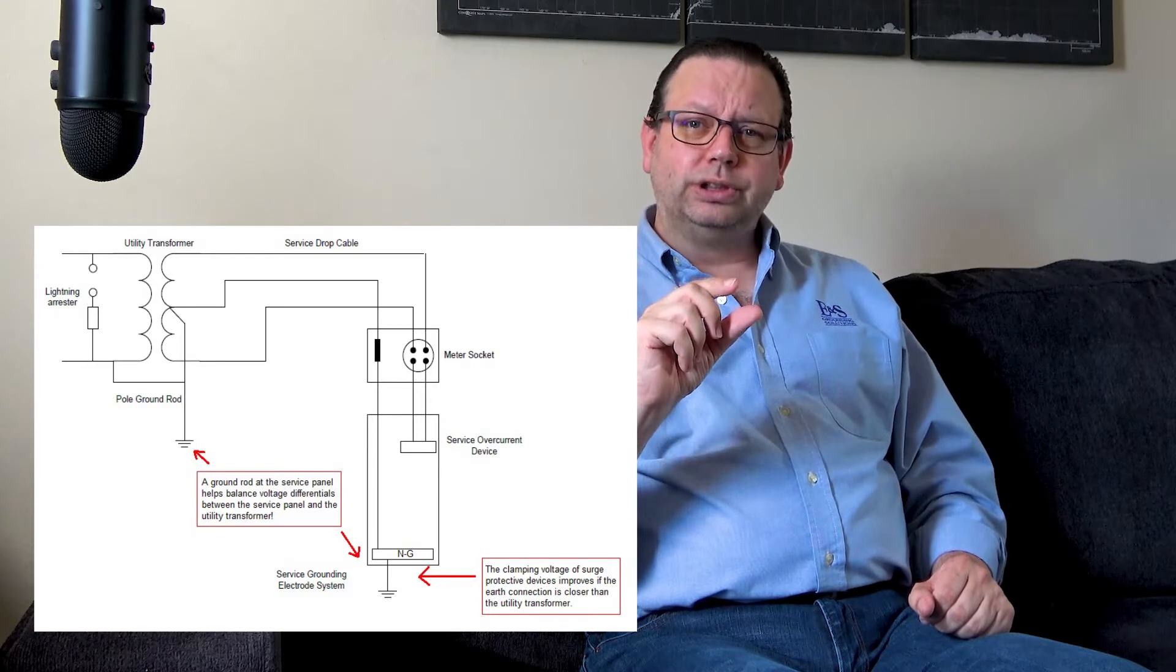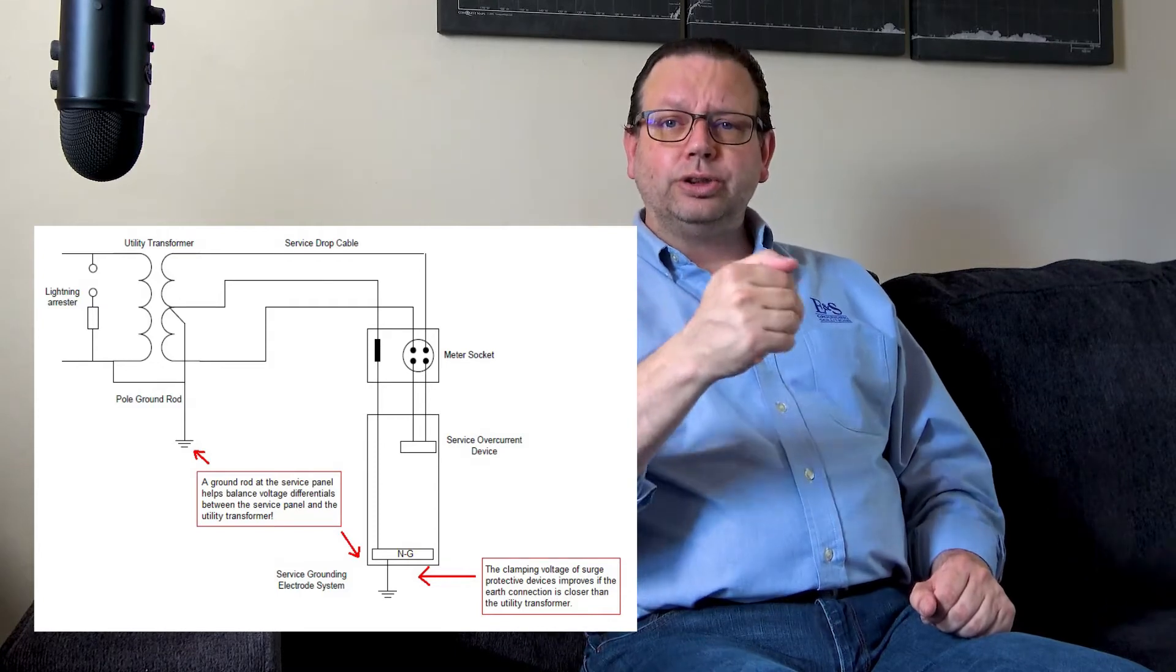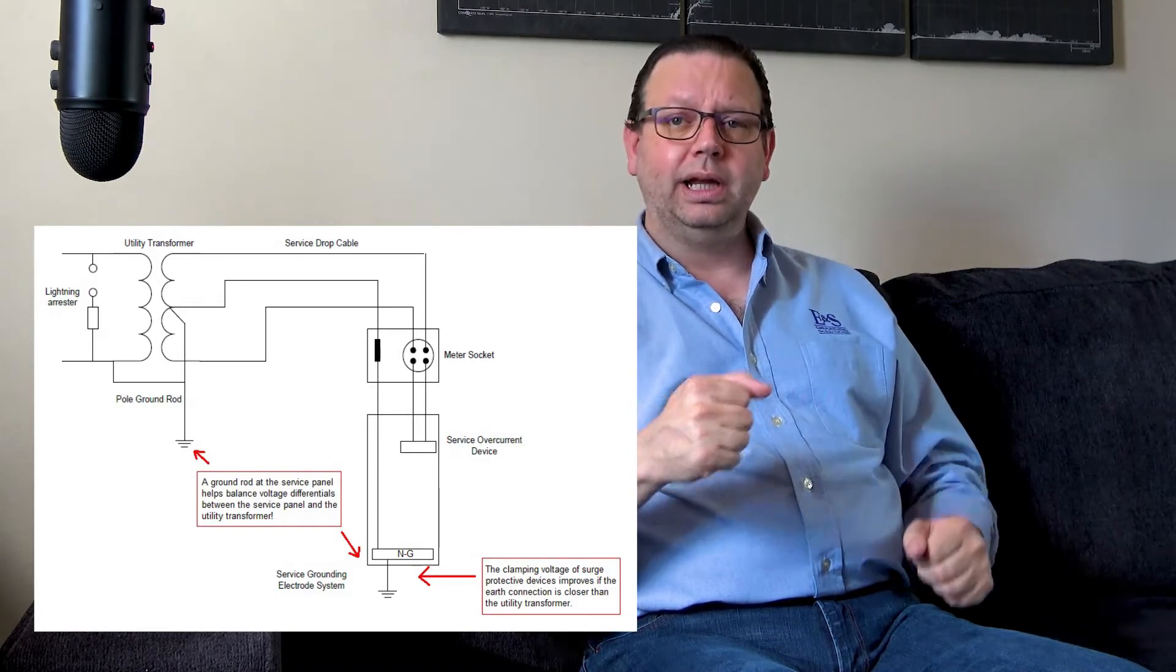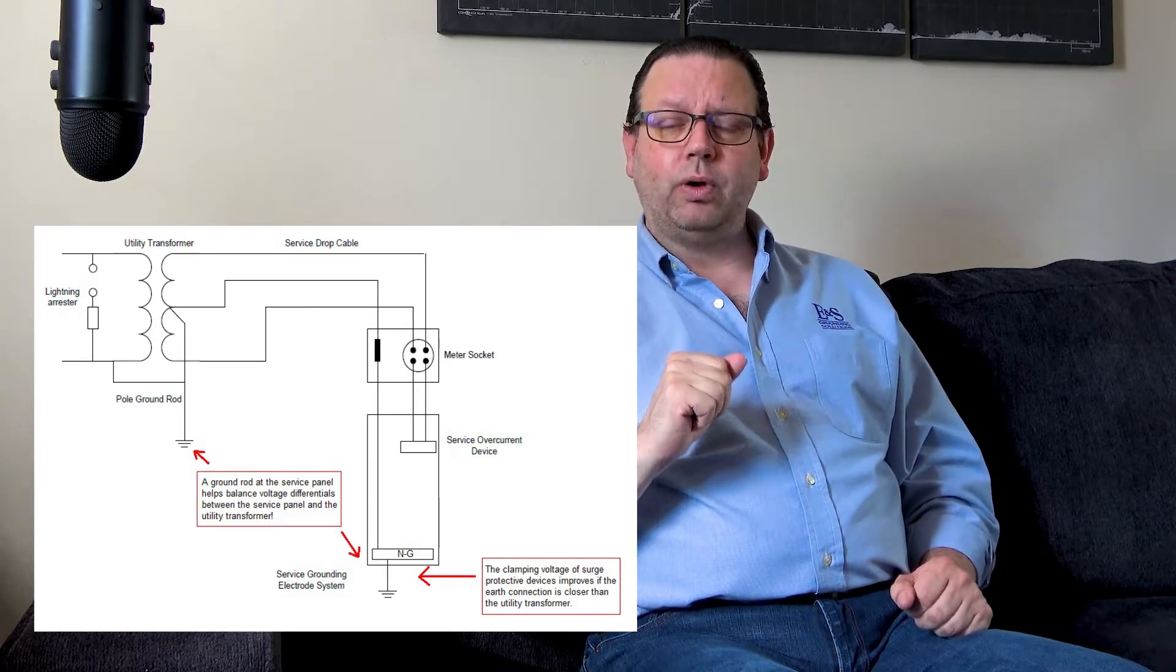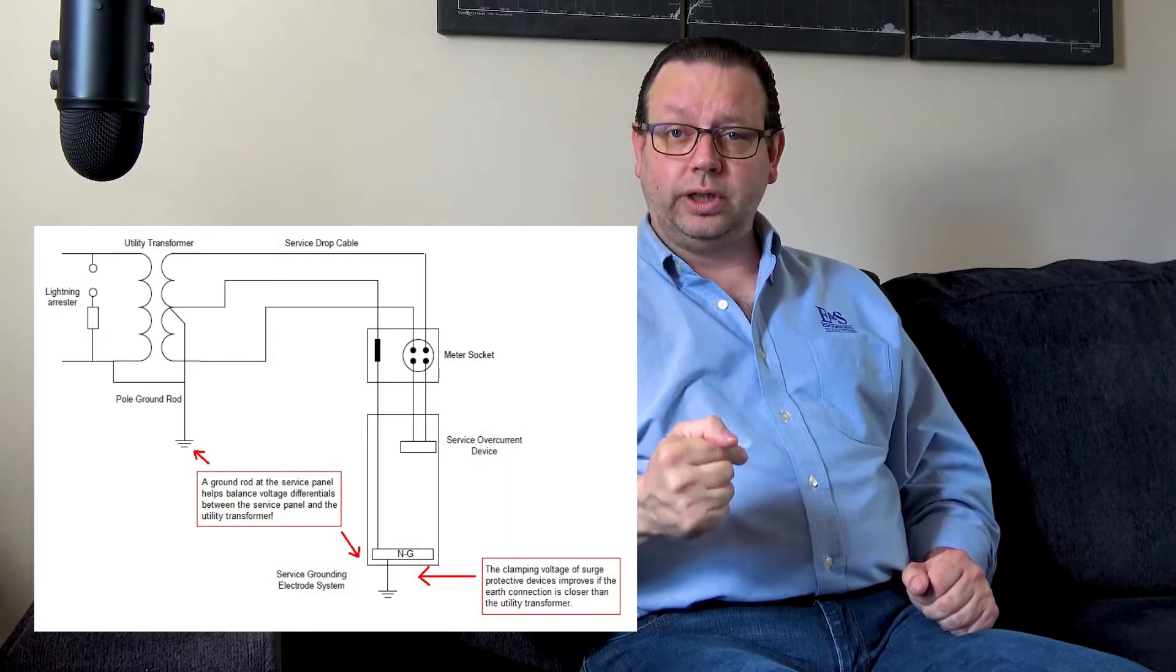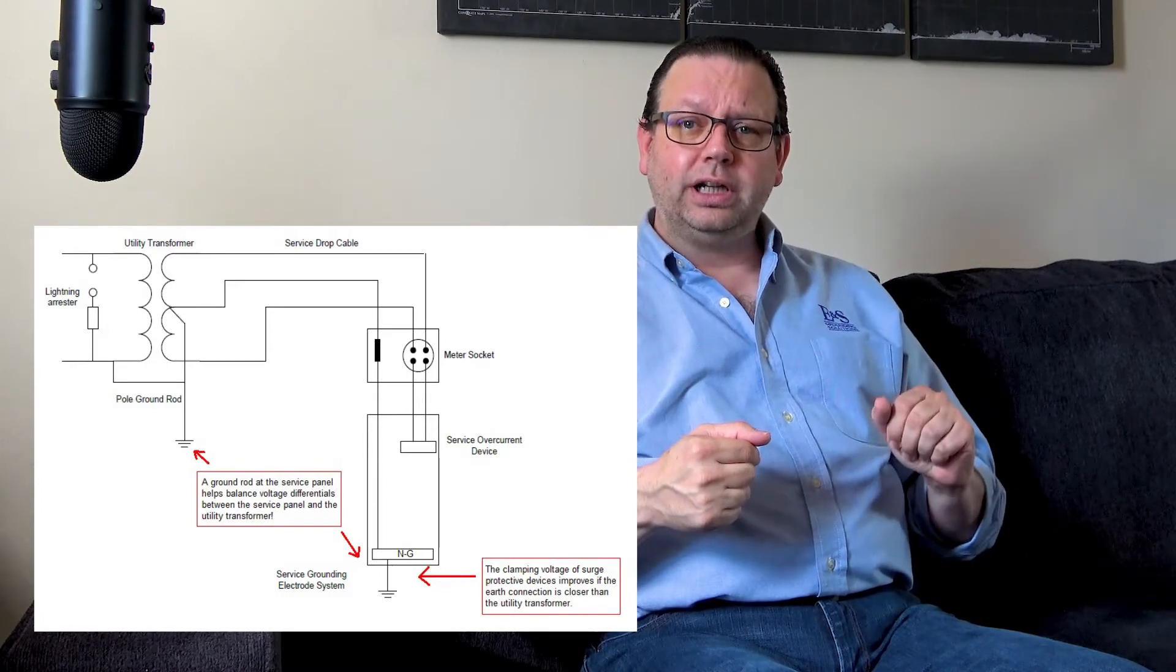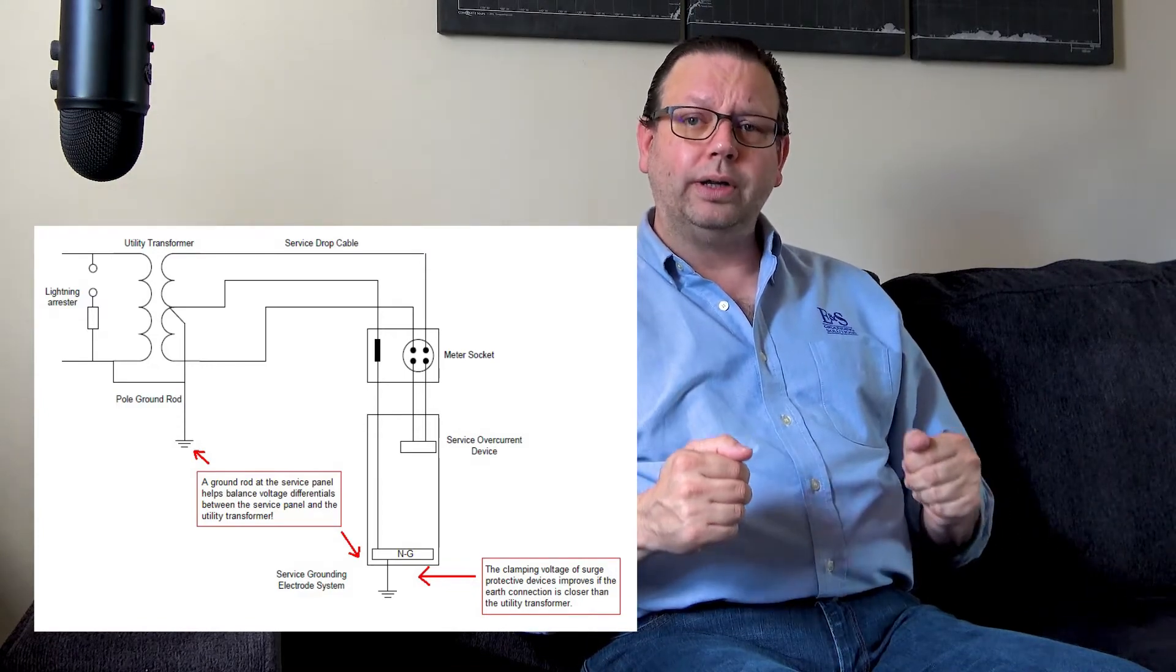Many of the reasons why is it has to do a lot with the operation of surge protection devices. So the clamping voltages of a surge protection device are better the closer that earth connection is. It also helped to balance the voltage differentials between the transformers, which can be located quite some distance away, and your home. It also, when the high side of that transformer faults, it helps to make sure that that fault is cleared back to the utility company's circuit breakers.